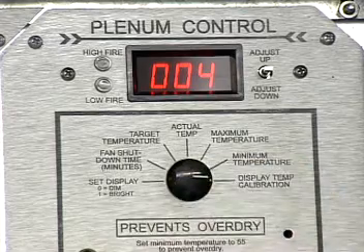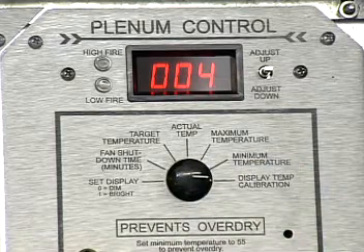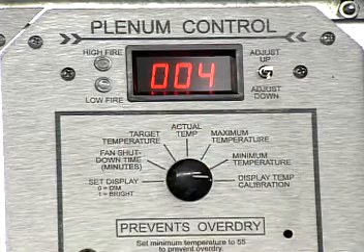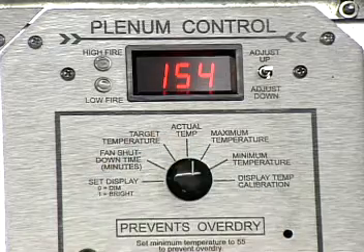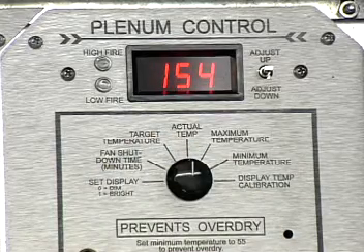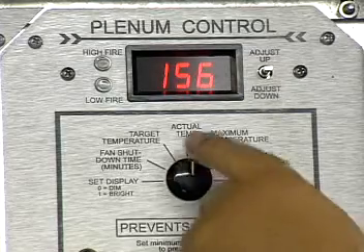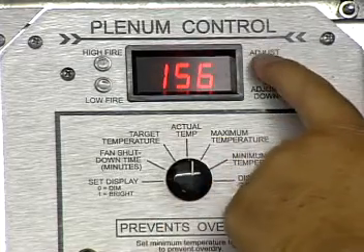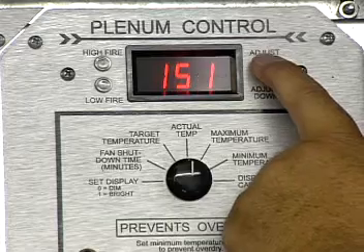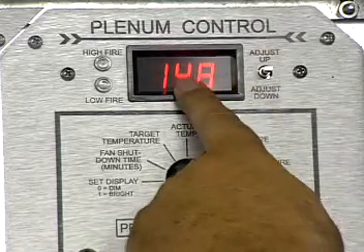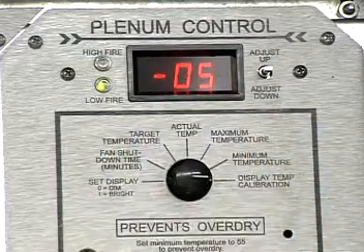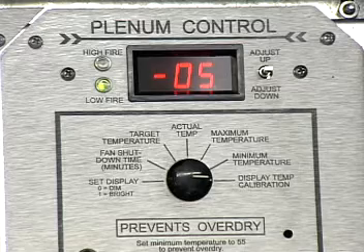Display temperature calibration. Right now we have a +4 degrees in there. If you have an actual temperature gauge thermometer that you're looking at someplace, we have it right here. It says it's 154, and the one that you're looking at says it's 148. I'd probably believe that one. In this position, we want to go down to 148. Now the two match. This matches with the thermometer. This will tell you that you lowered it now 5 degrees.